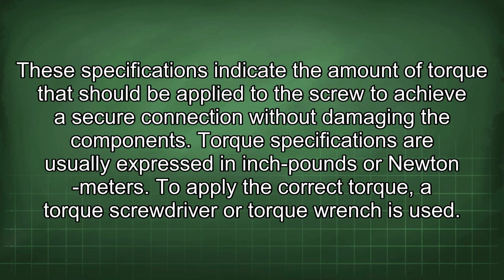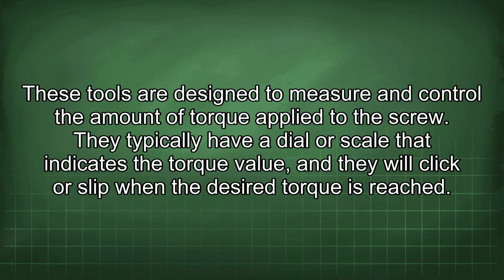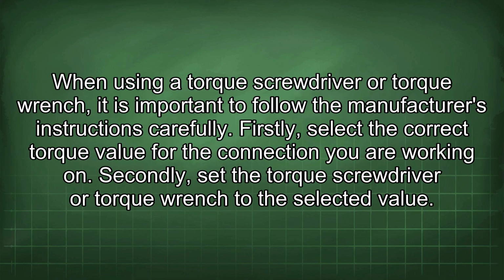These specifications indicate the amount of torque that should be applied to the screw to achieve a secure connection without damaging the components. Torque specifications are usually expressed in inch-pounds or Newton-meters. To apply the correct torque, a torque screwdriver or torque wrench is used. These tools are designed to measure and control the amount of torque applied to the screw. They typically have a dial or scale that indicates the torque value, and they will click or slip when the desired torque is reached.